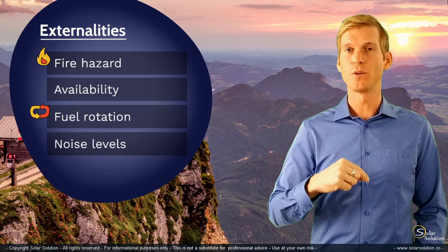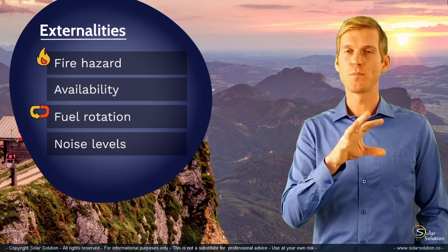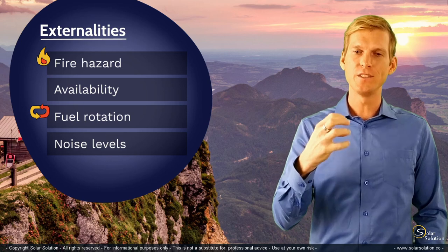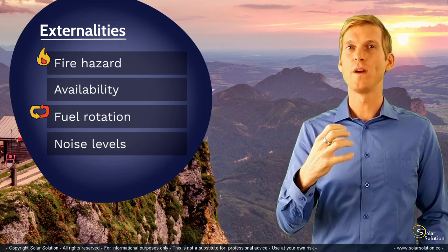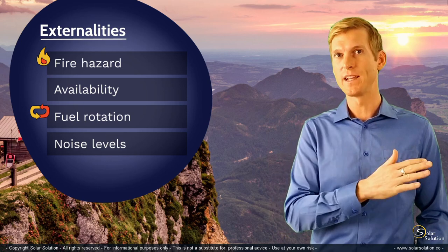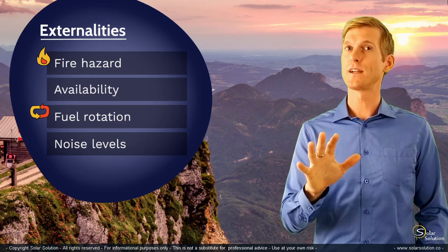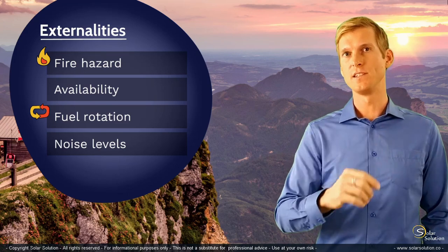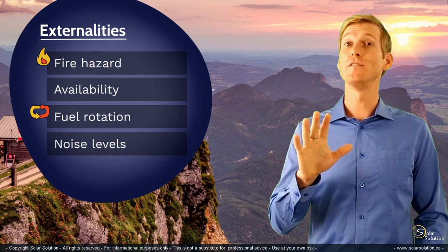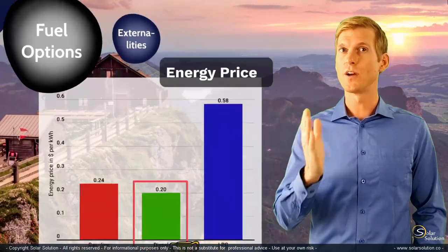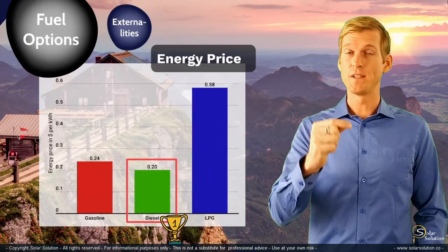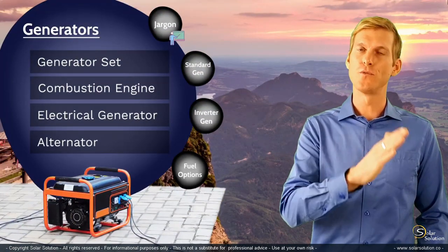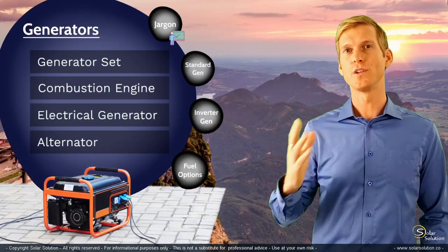The last point is noise levels. Diesel engines work with self-combustion — they don't have spark plugs to ignite the fuel — and therefore diesel engines are typically way more noisy compared to gasoline engines. So if noise is an important factor for you, you might want to stick with gasoline generators. These are just a few of the externalities to consider regarding the different fuel options, giving you an idea of what to expect from each fuel source.